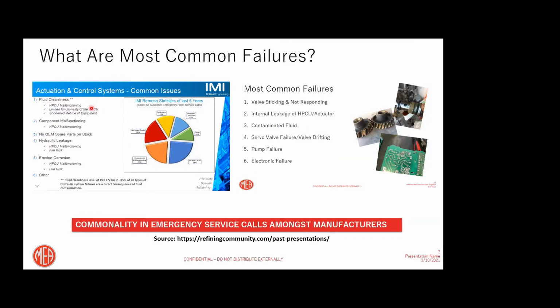So first of all, we see fluid cleanliness. If the fluids get contaminated, it affects the performance and causes malfunctioning of the components, one of which is the servo valve. If there is a lot of debris in the fluid, the little filter in the servo valve gets clogged, which causes malfunction and then valve drifting. That's the main issue, and we see that it's the issue for most of these units. It doesn't matter who makes them.